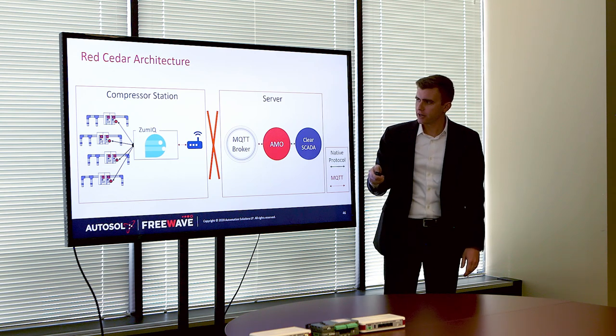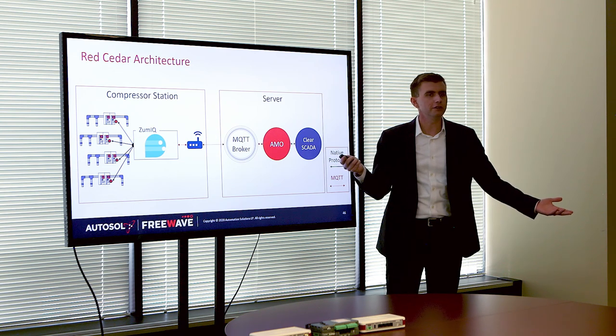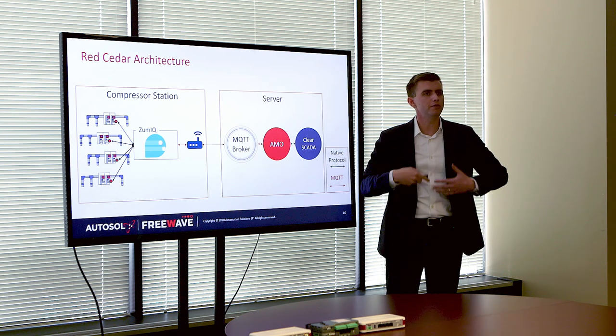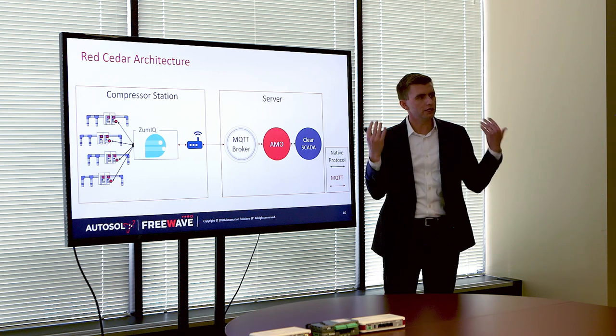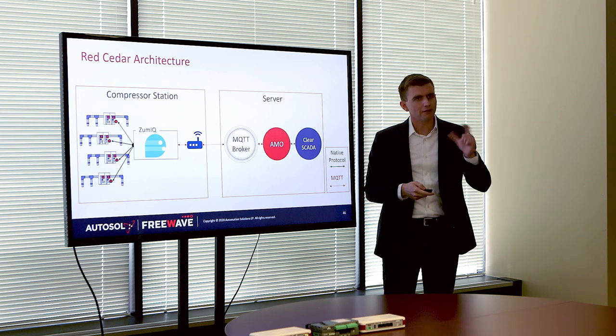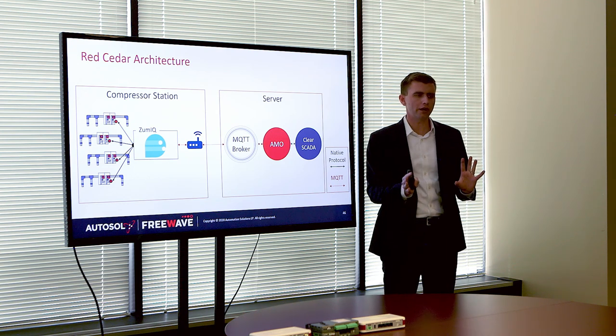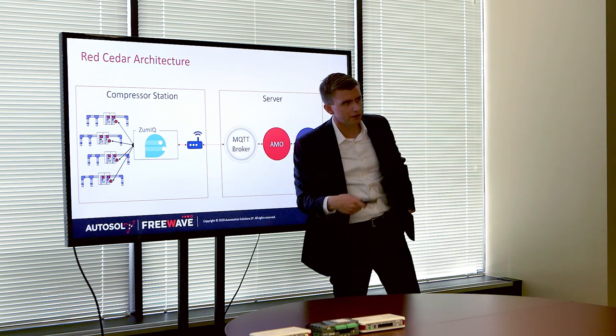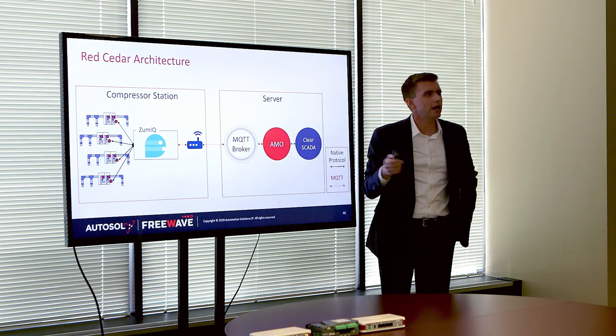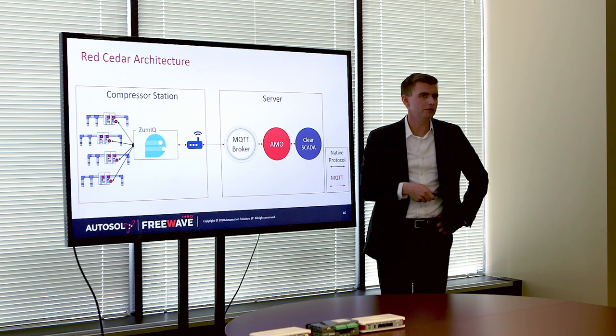When they lost communications, we were basically able to backfill everything in ClearSCADA. So when the EPA auditors showed up, they looked at the history of the points and there was no missing data. We can even flag the quality of the backfilled data as a different quality so they know this data was good because it was pulled successfully in the field, but it was backfilled during a comm outage. And from what I understand, that is acceptable to the EPA.